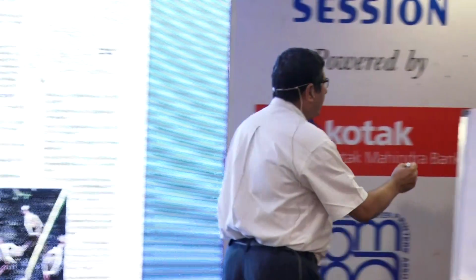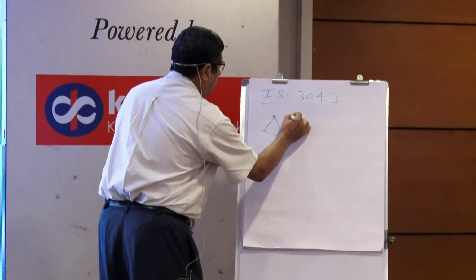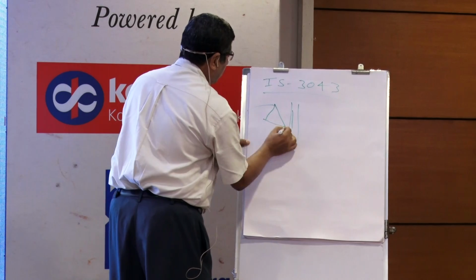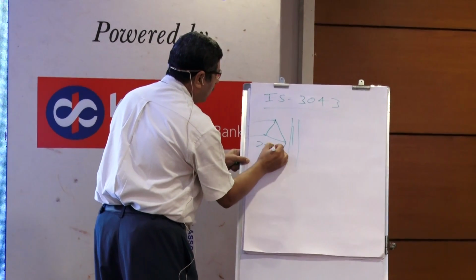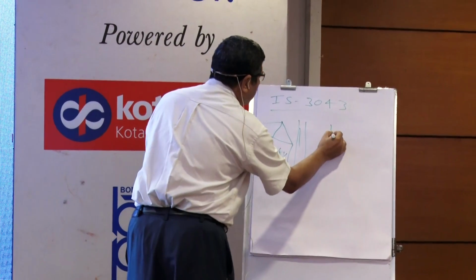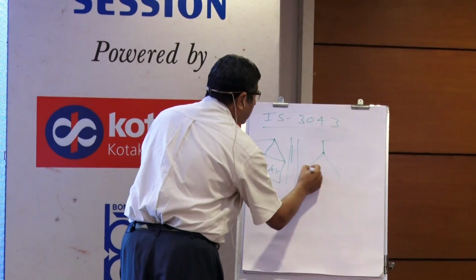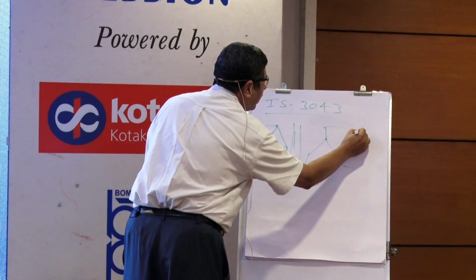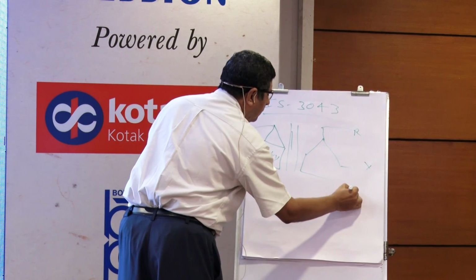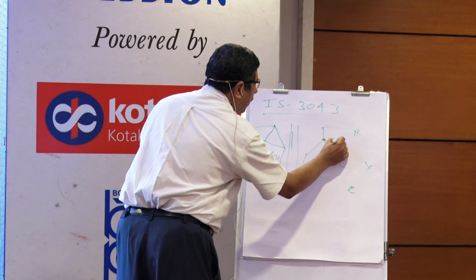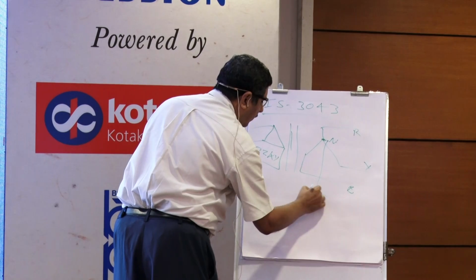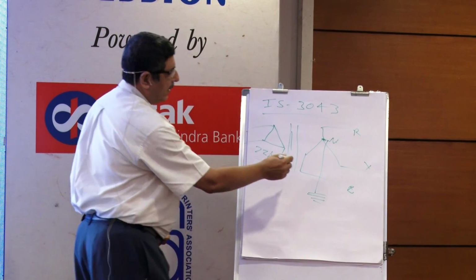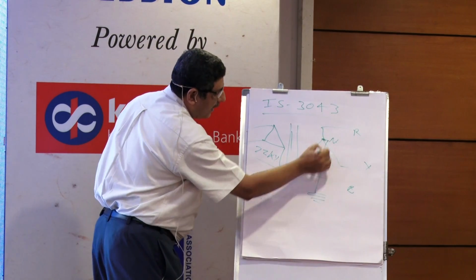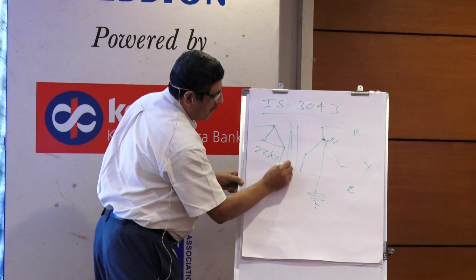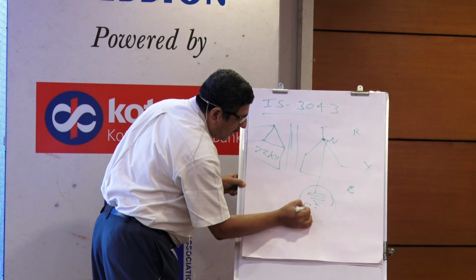When I say neutral grounding, as mentioned, we have a transformer with incoming supply. You have a three-phase line, 22K, with a star connection. This connection going into your factory creates a point called the neutral point, and the earthing required for this is what we call neutral grounding. This point has to be connected, and this is only copper.